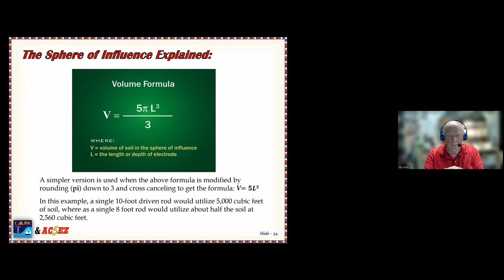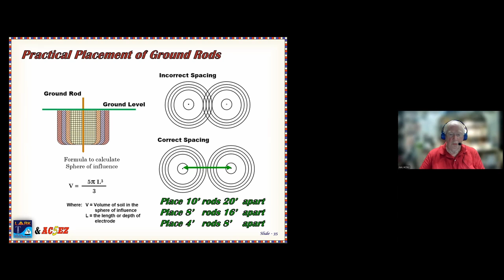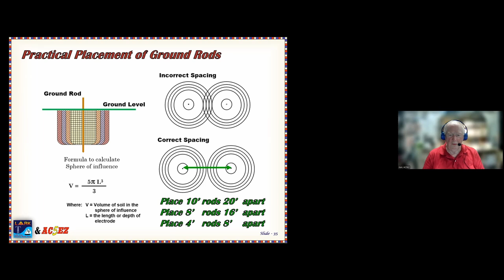And I'm not going to go through that because I'm running a little late here. I'm going to have to speed up. But if you were to ground your rods together, say from your antenna to wherever your circuit breaker box, and we normally buy 8-foot ground rods, you could space those ground rods 16 feet apart, and you would get adequate ground coverage. Now, if you get them too close, you're wasting space, or if you go too far, you might have a little resistance potential between the two. But for 8-foot rods, you could space them 16 feet apart. It would give you ample coverage.